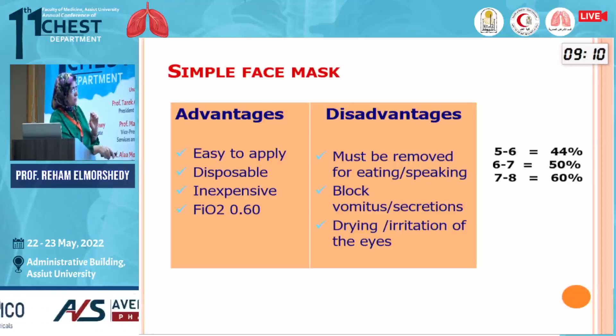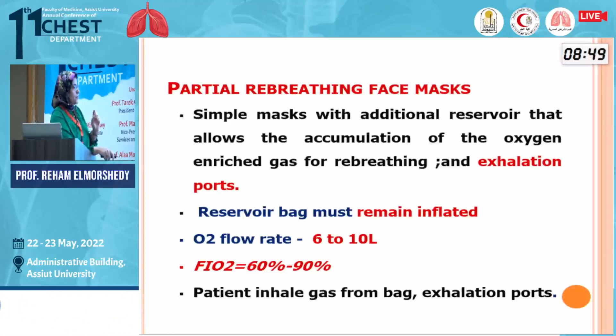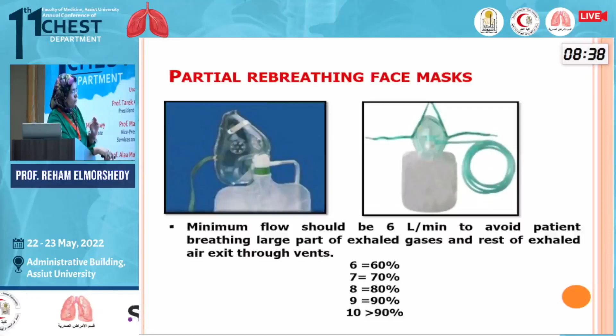Partial rebreathing face masks, these are simple masks with additional reservoir bags that allow the accumulation of oxygen for rebreathing, and it has 2 exhalation ports. The reservoir bag must remain inflated, an oxygen flow rate up to 10 liters, and it delivers a fraction of inspired oxygen up to 90%. So this is the partial rebreathing mask with reservoir bag with 2 exhalation ports. The minimum flow should be at least 6 liters per minute to avoid breathing large amounts of exhaled gases and CO2 rebreathing.